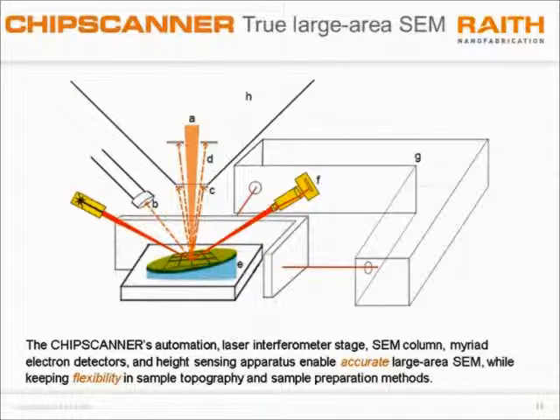I mentioned the automation. Large area imaging takes a lot of time, just like electron beam lithography. And it is required that these instruments reliably run unattended overnight, even over a few days, capturing these images over large areas. The laser interferometer is a critical ingredient to the chip scanner. This is a high precision stage that can measure the sample position down to 1 nanometer. It uses laser beams that are incident on a very carefully manufactured mirror. The reflected beams go back and are interfered with a reference beam, and this is a way to measure the plane of the sample with very high accuracy and precision down to 1 nanometer.